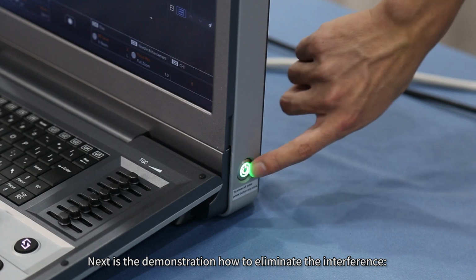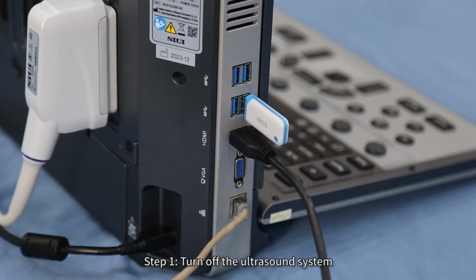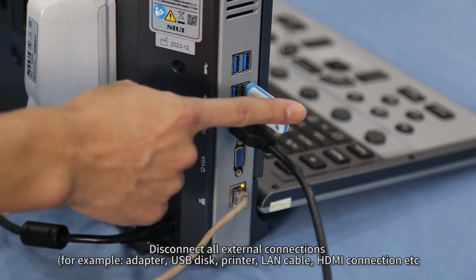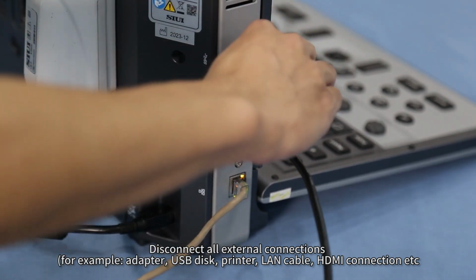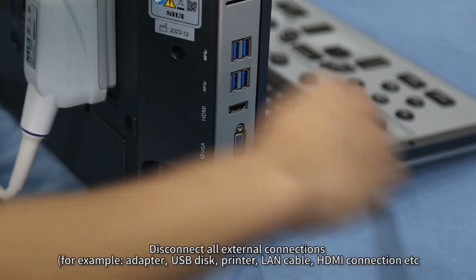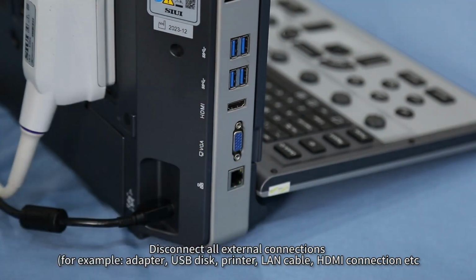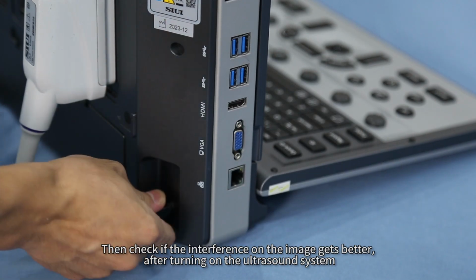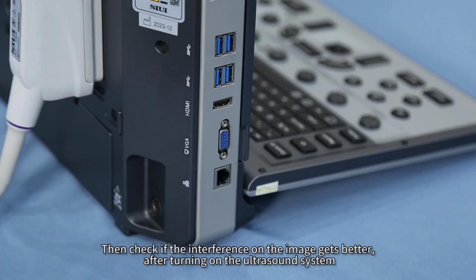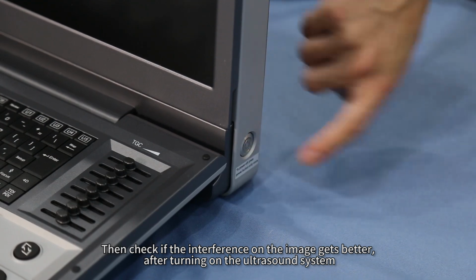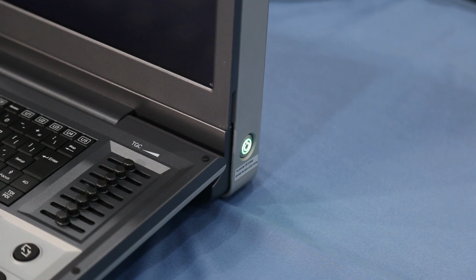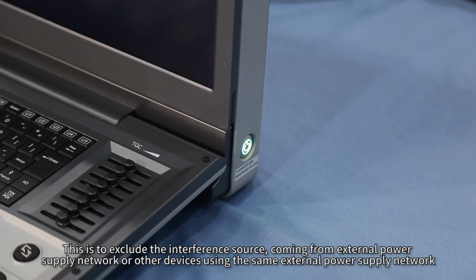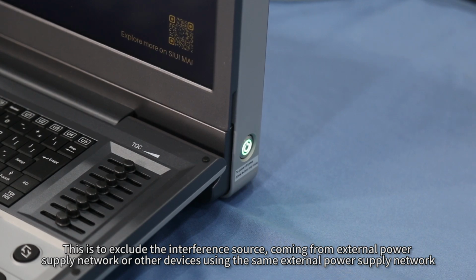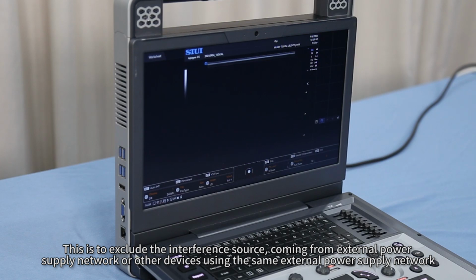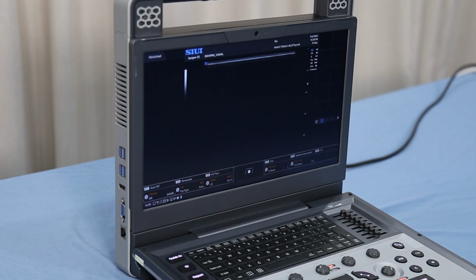Next is the demonstration of how to eliminate the interference. Step 1. Turn off the ultrasound systems. Disconnect all external connections, for example, adapters, USB disk, printer, LAN cable, HDMI connection, etc. Then check if the interference on the image gets better after turning on the ultrasound systems. This is to exclude the interference source coming from the external power supply network or the other devices using the same external power supply network. And if this step doesn't help, move on to step 2.